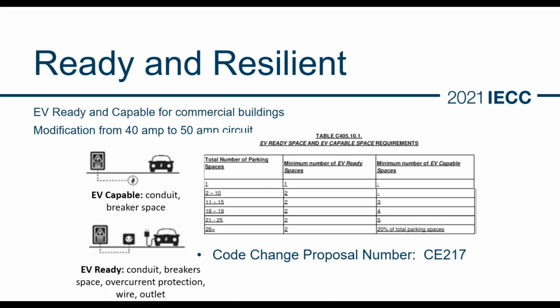The other thing we're getting into now is electric vehicle charging stations. This actually passed in the main body of the code, CE 217. It would require a certain amount of spaces to be both EV capable and EV ready. EV capable essentially requires conduit and breaker space, so you can just run the conduit to the parking space, whereas EV ready requires conduit, breaker space, overcurrent protection, wire and the outlet, but you don't actually have to install the actual charging part, just make sure everything's in place. So CE 217, again, did pass, and this is being challenged by public comment.